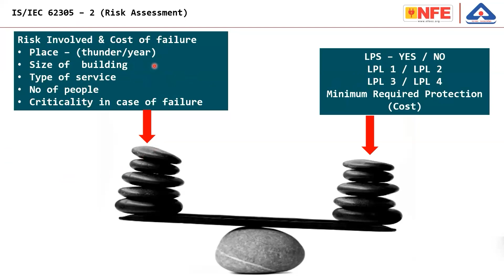Now, if you require lightning protection, it is divided into 4 levels: LPL 1, 2, 3, 4. The whole story of risk assessment is a calculation based on the number of thunderstorm days, size of building, type of service, number of people, and criticality in case of failure. Finally, on one side, we are finding out how much money or economics is involved in case of a lightning strike and its related failure. On the other side, how much money you are going to spend to protect a building. And in the middle, you have the tolerable risk.